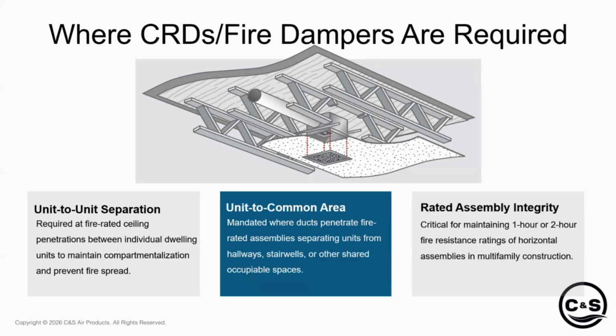A couple things about the rated assembly integrity: wood truss ceiling radiation dampers are only listed for 1 hour. So for, I would say, 95% of all apartment jobs that are built in the US that are wood construction, they're all going to be a 1 hour rating. Anything that you see above 1 hour is typically a non-combustible ceiling space, like a T-bar ceiling, where the radiated heat will eventually do some damage to the space above, but it won't be quite as critical as that 1 hour you have for wood truss, where that wood construction starts to self-combust at certain temperature ranges, even if fire actually isn't up in the ceiling space.